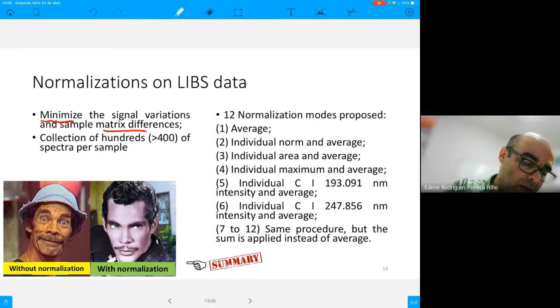These normalizations, the goal is to minimize the signal variations and sample matrix differences. I suggest, for instance, to collect more than 300 or 400 spectra per sample, and we are performing several normalization modes in order to minimize these problems related to micro heterogeneity. For example, the average is not a normalization, but when you have several spectra, for example, hundreds of spectra, we can minimize problems with heterogeneity.